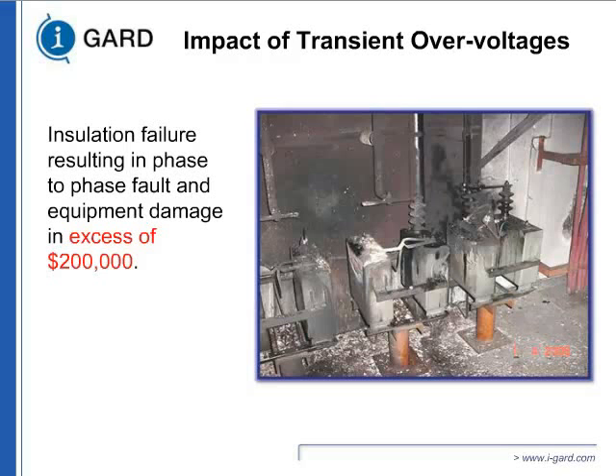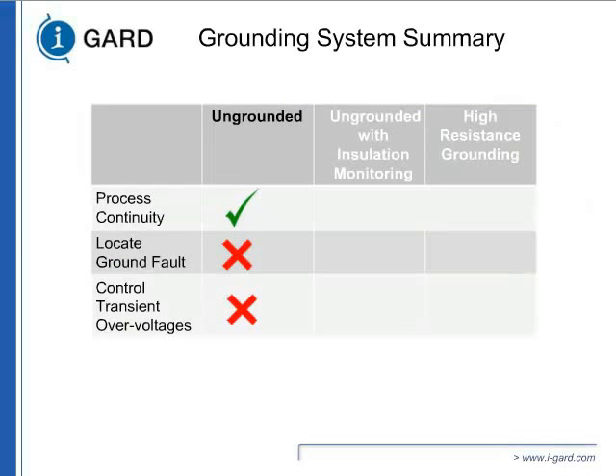If you use ungrounded, the reason we used it was that we needed process continuity. In the petrochemical or continuous process industry, an unintentional outage can create an environmental impact and a safety impact. That's the reason the delta system became popular, because it allowed us to sometimes locate the fault by shutting things down, or avoid an outage for a while. The only advantage there was process continuity, and that helps us in safety.